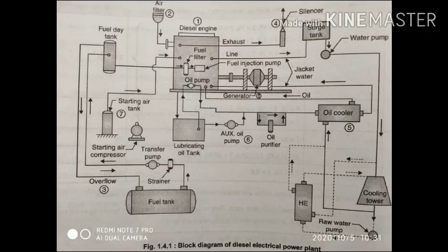In the cold season, the intake air is heated by heat from exhaust gases before injection. The filters are to be cleaned periodically. Superchargers are usually placed in between the engine and the intake since the noise may be transmitted back to the outside air via the air intake system. There should be minimum pressure loss in the air intake system, otherwise specific fuel consumption will increase and the engine capacity will be reduced.